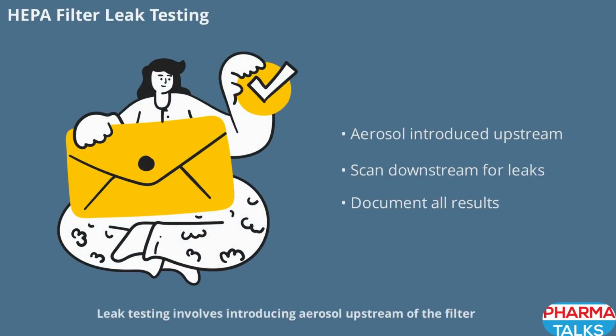Leak testing involves introducing aerosol upstream of the filter and scanning the downstream surface for any signs of leakage. Acceptable leakage limits are defined by regulatory standards, and any results outside these limits must be addressed immediately. All test results must be documented to demonstrate ongoing compliance and filter integrity.